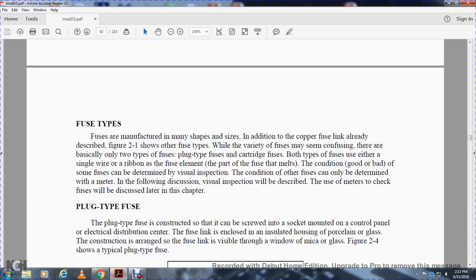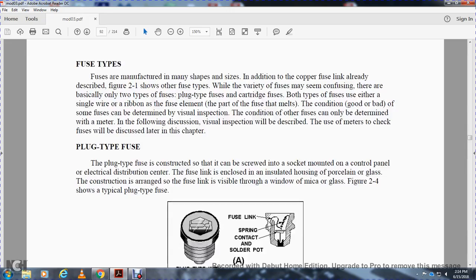All right, fusible types. Fuses are manufactured in many shapes and sizes. In addition to the copper fuse link described in Figure 2-1, there are other fuses with a variety of types that may seem confusing. But there are basically two types of fuse: the plug type and the cartridge fuse. Both types have either a single wire or ribbon fuse element - the part of the fuse that melts. For some fuses, the condition - good or bad - can be determined by visual inspection. The condition of other fuses can only be determined with a meter. The following discussion on visual inspection will describe using meters to check a fuse, which we'll discuss later in this chapter. The plug type fuse is constructed so that it can be screwed and secured, mounted on a control panel or electrical distribution panel. The fuse link is enclosed in an insulating housing of porcelain or glass. The construction arranges the fuse link to be visible through a window of mica or glass.